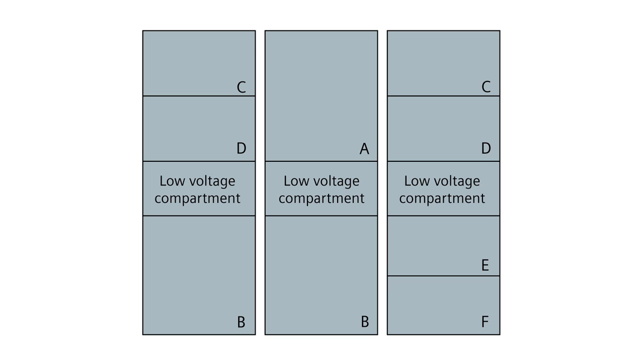Let's begin by looking at the skeleton, which is offered in three basic configurations and in a variety of stacking options for your switchgear project. No matter which structure you implement, OEM partners need to design and add approximately 28 inches of structure for the terminal compartment, plus bus bars and front and rear doors. This vertical section can then be bolted to additional vertical sections side by side.